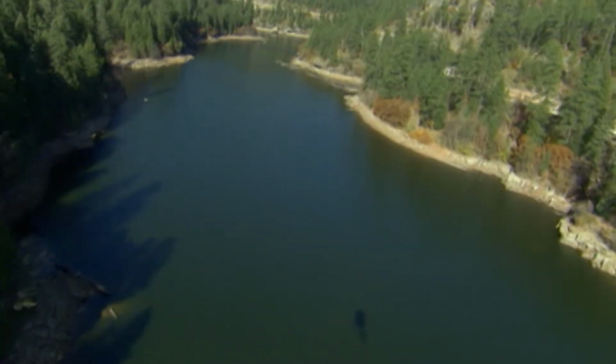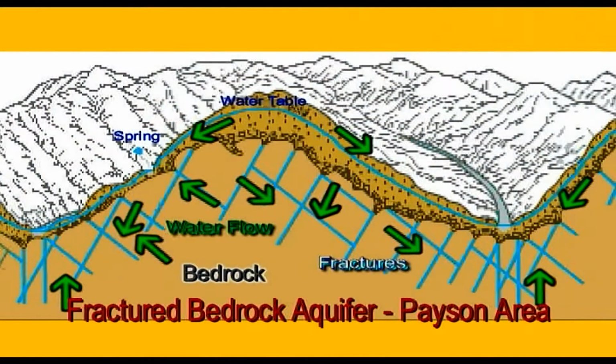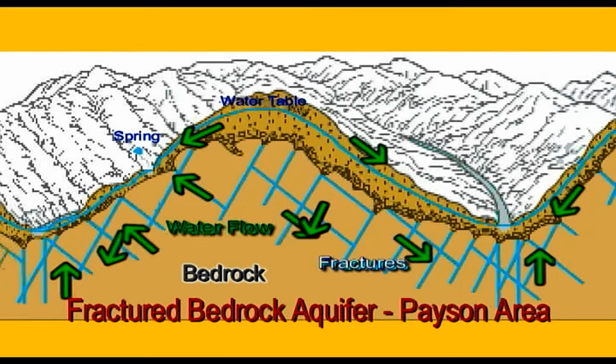The water would also have to be buffered because the new surface water is entering a groundwater system where the groundwater has been in contact with underground minerals and deposits and would have a tendency over time to harm the existing system. The well water is a harder water, it has high alkalinity. The C.C. Cragin water is actually a very soft water, it has a very low alkalinity. We did some chemistry adjustment to our water where we added alkalinity to it and we adjust the pH. And so we actually get a net neutral water that's not going to deposit on the piping, but it's also not going to dissolve any minerals. So that neutral water makes it so our water is not going to have an impact on the piping system or the wells.